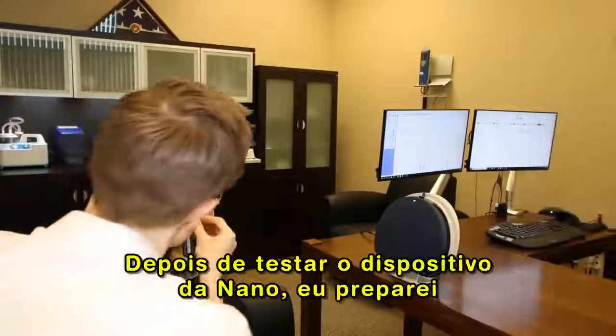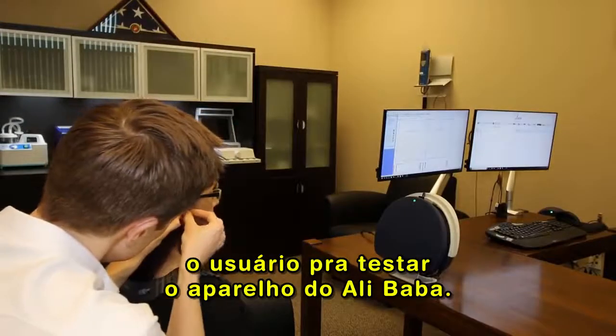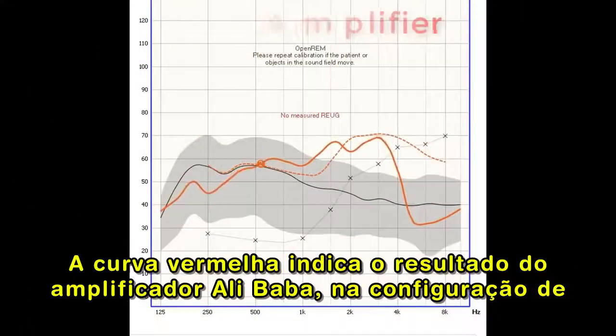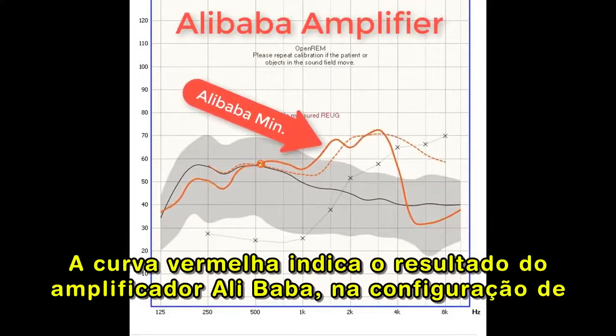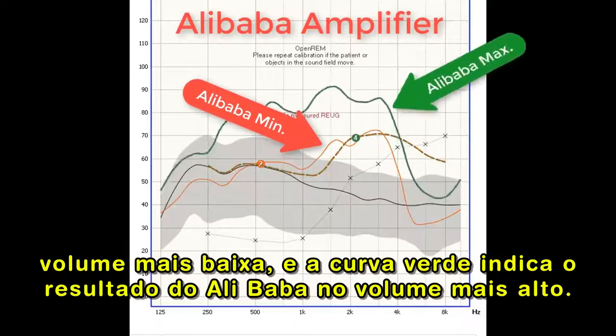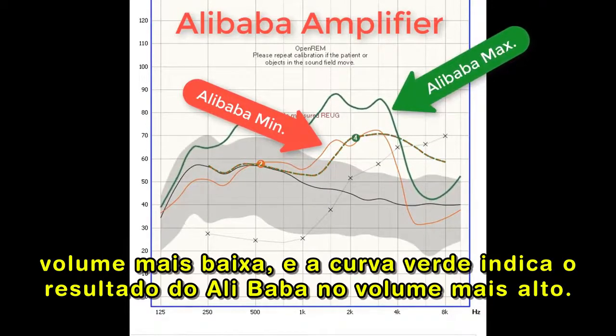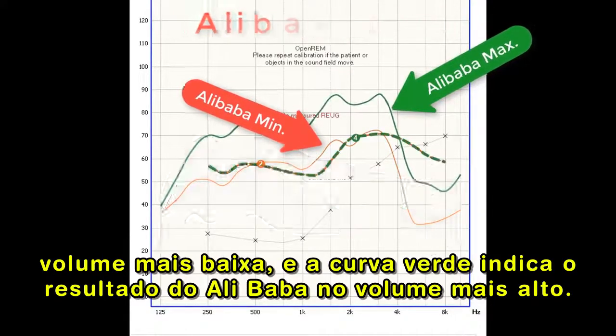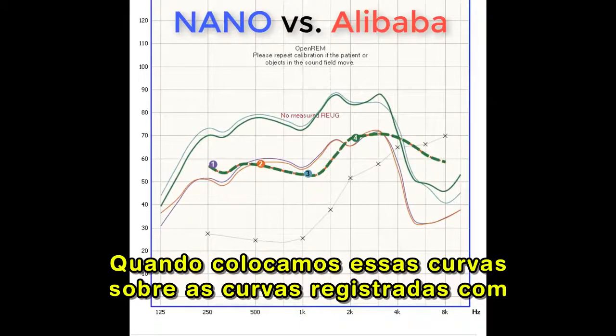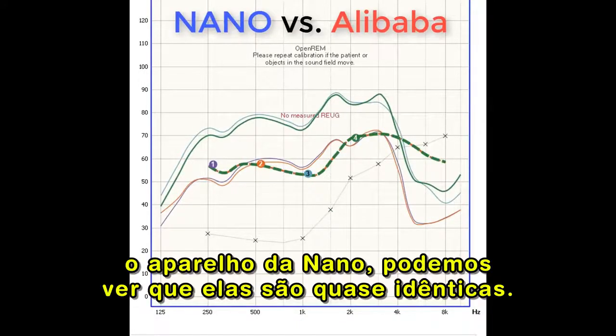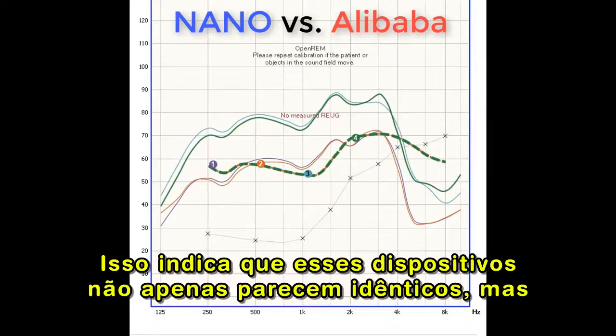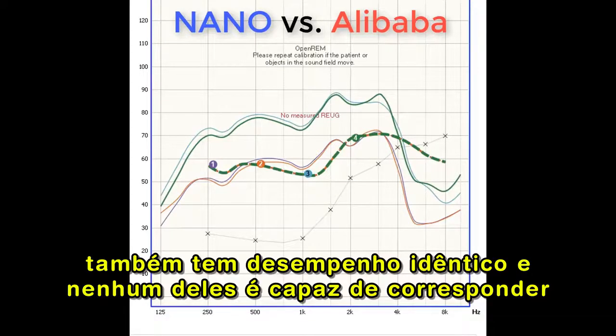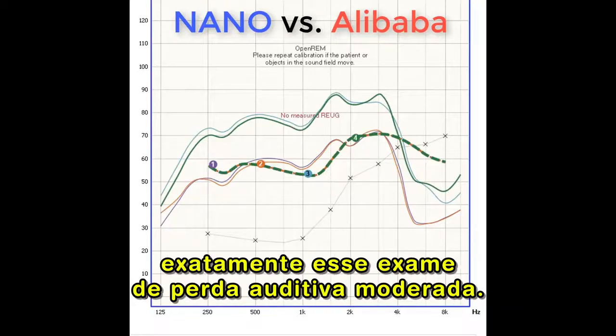After testing the nano device, I then set up the user to test the Alibaba device. The red curve indicates the output of the Alibaba amplifier at the lower volume setting, and the green curve indicates the output of the Alibaba amplifier at the highest volume setting. When we overlap these curves with the curves recorded with the nano hearing aids, we can see that they are almost identical to each other. This indicates that these devices not only look identical to each other, but they also perform identically to each other, and neither one of them is capable of exactly matching this moderate hearing loss prescription.